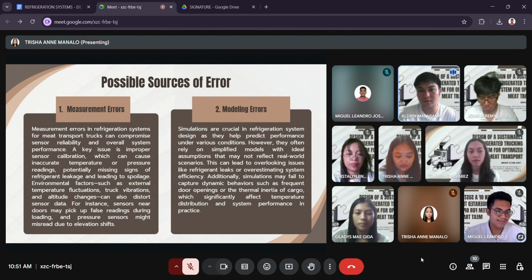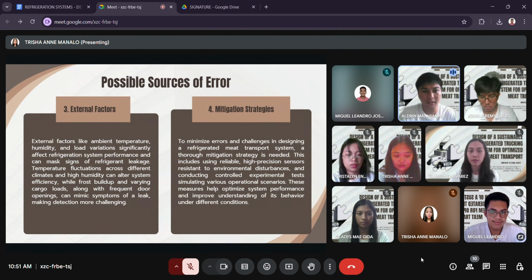Simulations are crucial in refrigeration system design as they help predict performance under various conditions. However, they often rely on simplified models with ideal assumptions that may not reflect real-world scenarios. This can lead to overlooking issues like refrigerant leaks or overestimating system efficiency. Additionally, simulations may fail to capture dynamic behaviors such as frequent door openings or the thermal inertia of cargo, which significantly affect temperature distribution and system performance in practice. Next slide po. And number three, external factors.